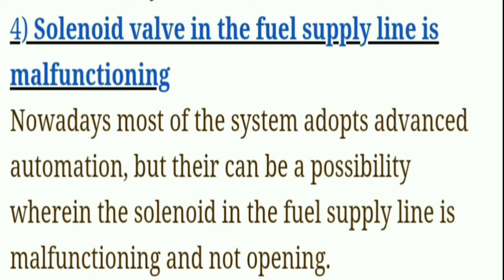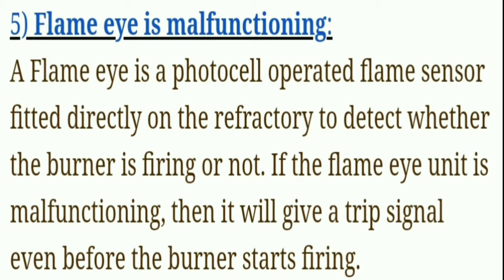Fourth, the solenoid valve in the fuel supply line is malfunctioning. Nowadays most systems adopt advanced automation, but there can be a possibility wherein the solenoid valve in the fuel supply line is malfunctioning and not opening.